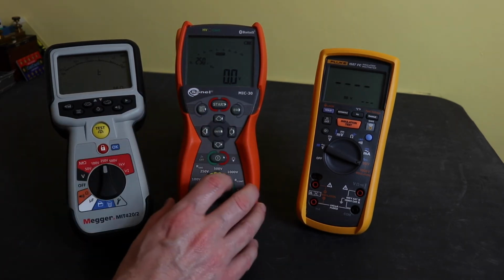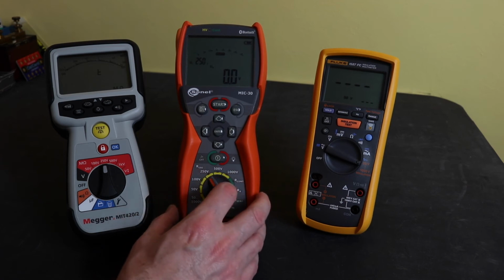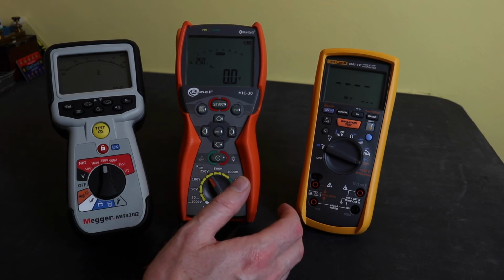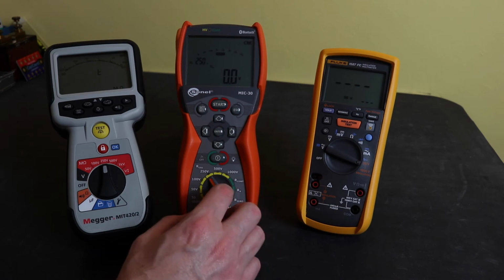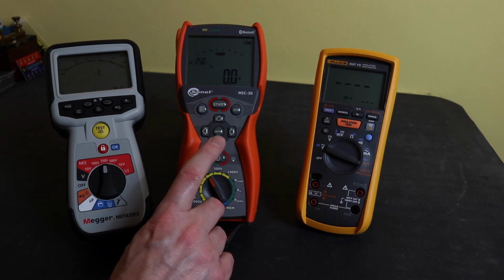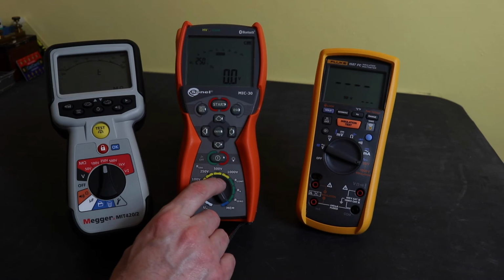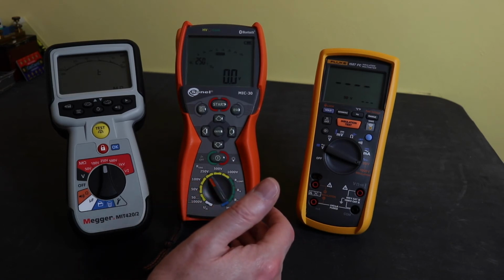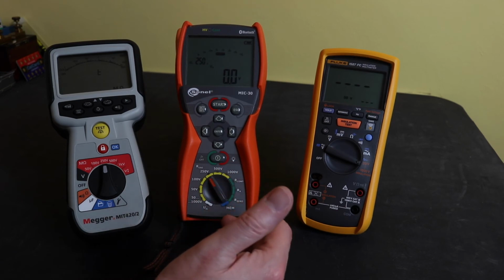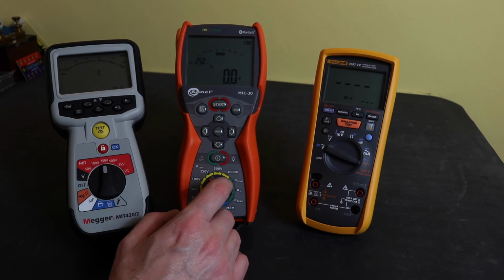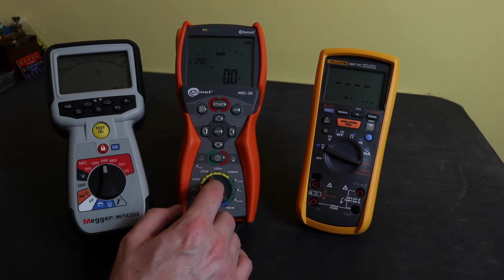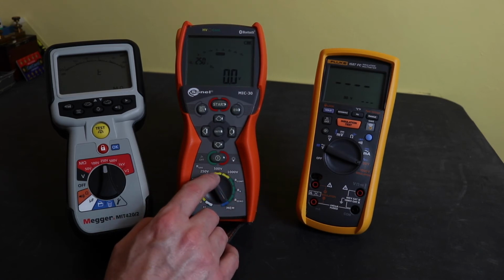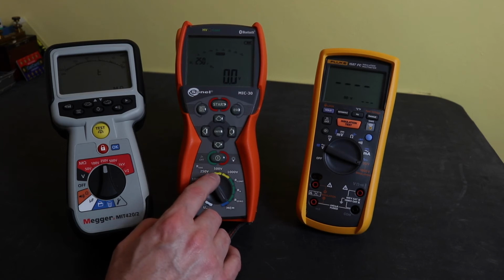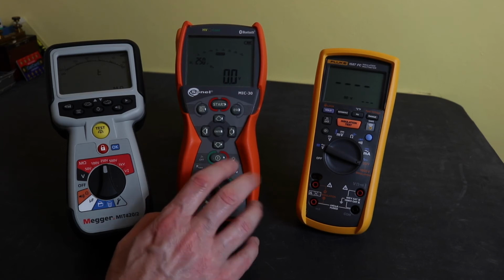The Sonel here, for modern day insulation systems, the IEC and IEEE standards allow me to go up to 5 gigaohms for the 1 minute. And generally speaking, the vast majority of DAR and PI ratios really will be sort of like 2 to 3. So that will put you in the 15 gigaohms region. So you will get away with PI testing the majority of times at 500 volts with this instrument.